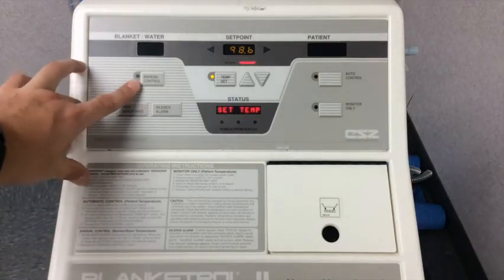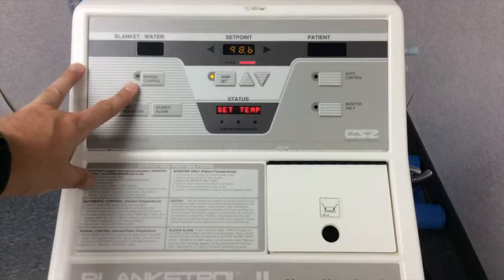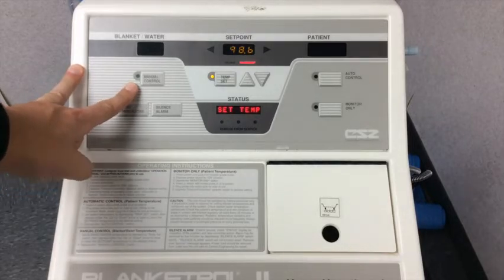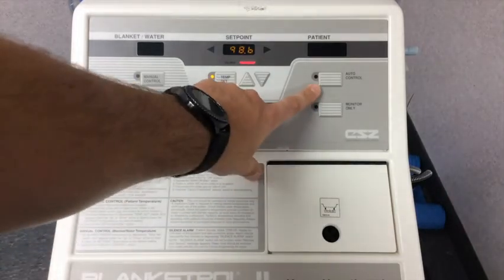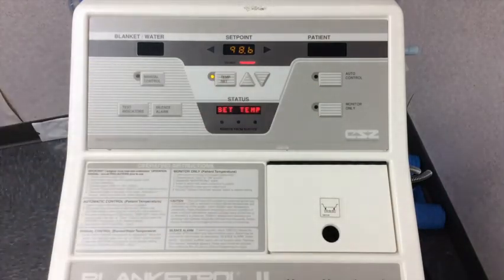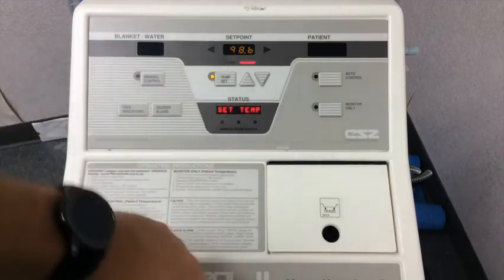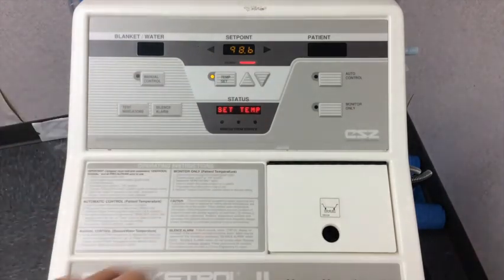Manual control simply controls the temperature of the water. It does not take into consideration any patient involvement. Auto control will utilize the temperature probe, and it will auto titrate the water temperature to best get the patient to the current set point. And then the third option is monitor only, which simply takes the patient's temperature without circulating any water.